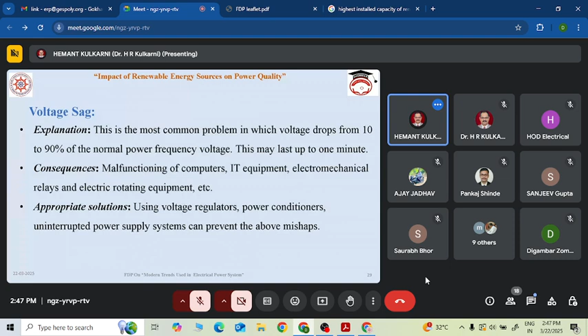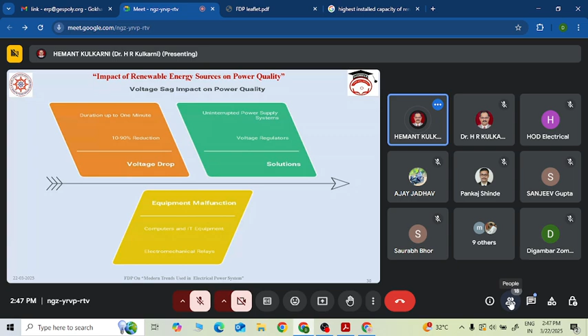You can get this voltage sag - just now I explained what voltage sag is. Voltage sag means it is a voltage drop, up to 10 to 90% reduction, with duration up to 1 minute. So what are the consequences of that? There is equipment malfunction - computers and IT equipment get affected, and electromechanical relays may get affected because of this.